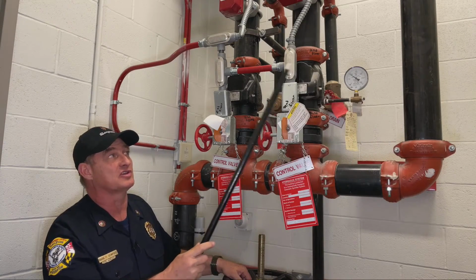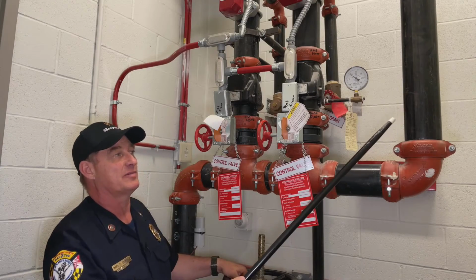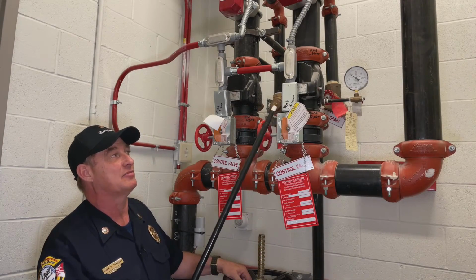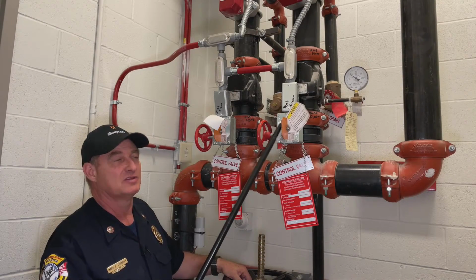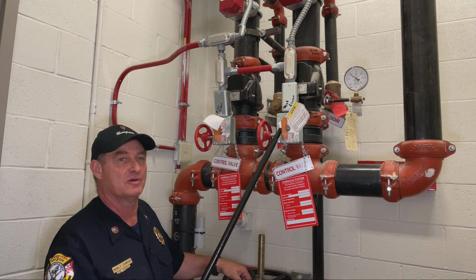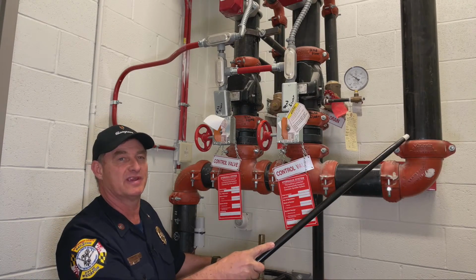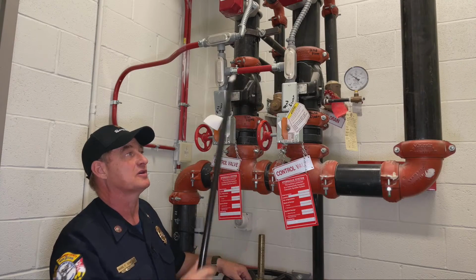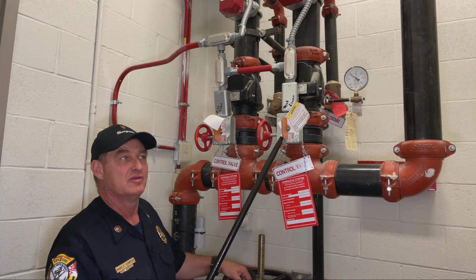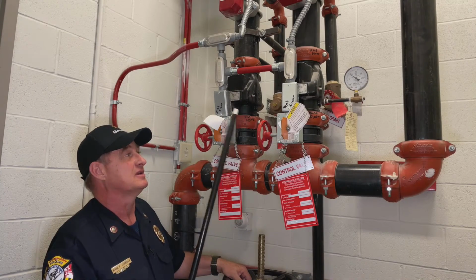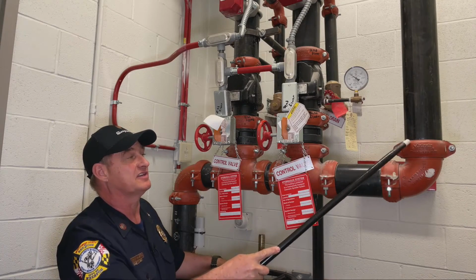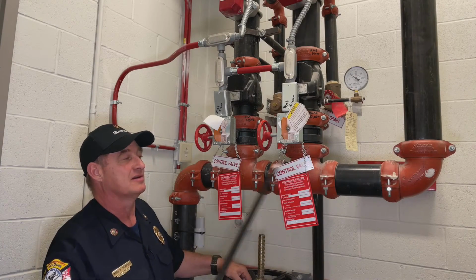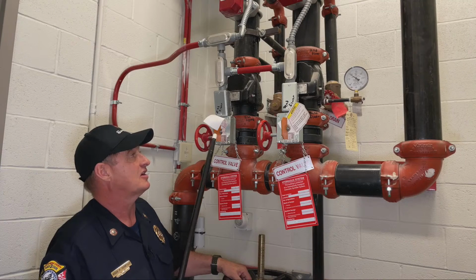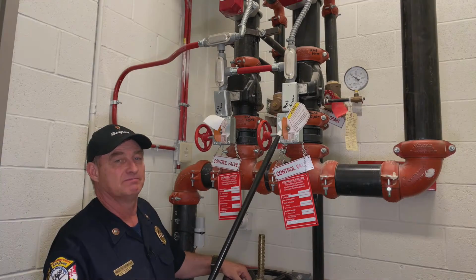In a single zone system, the fire department connection is always going to tie above this control valve. So if this control valve was closed, you could simply pump into the FDC and circumvent this closed valve. But in a multi-zone system, the FDC is going to tie into the header, and you may need to come and open valves.